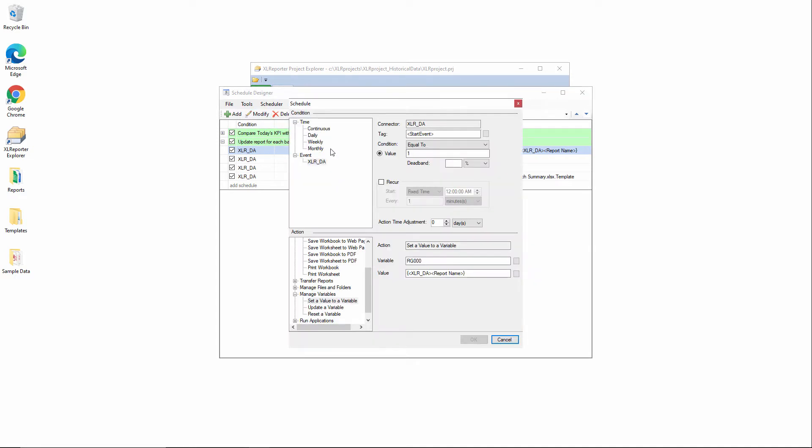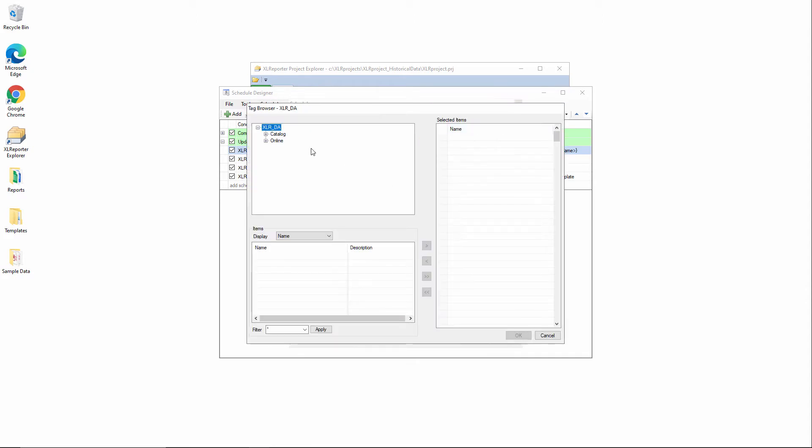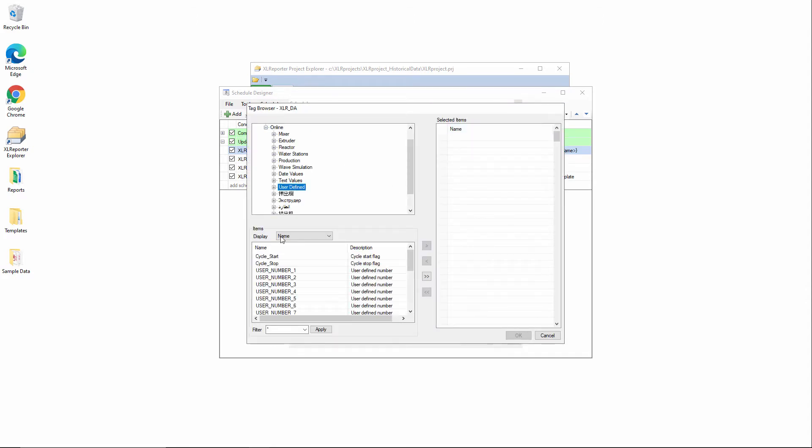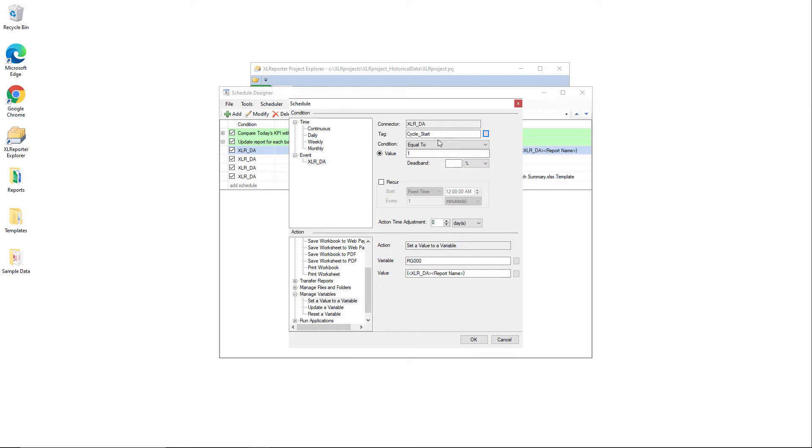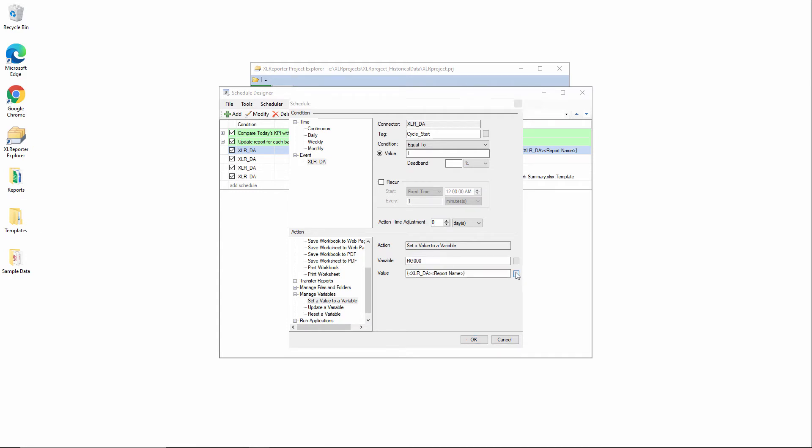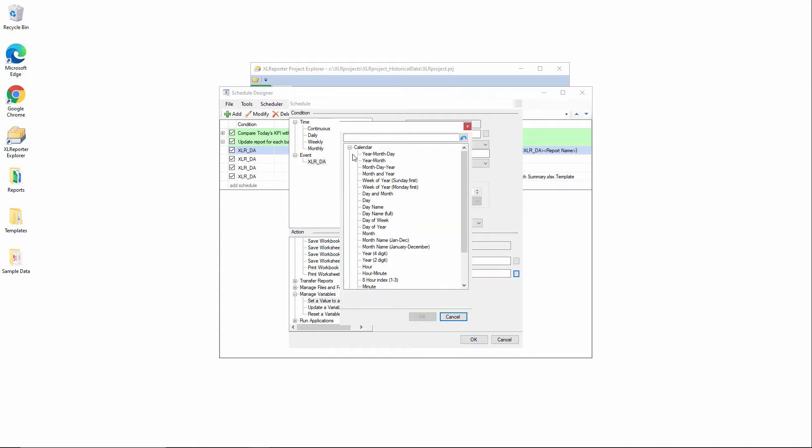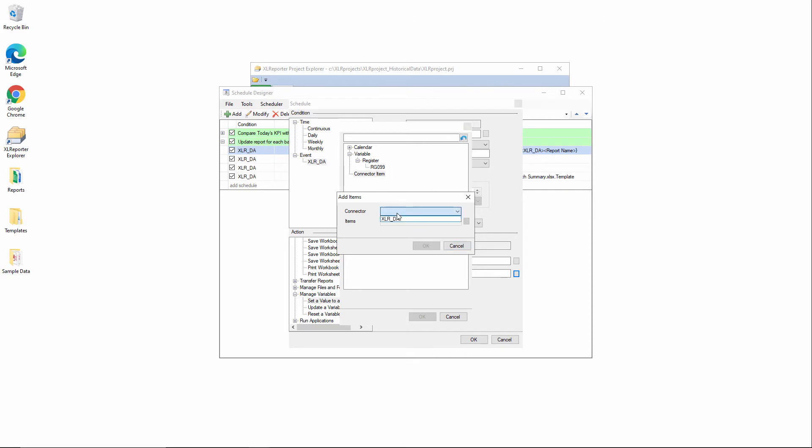I'll select the event condition under my PLC connector with a tag. Let's do, for example, cycle start using the XLRDA simulator here. I'll copy that tag name out because we'll use it for the other three actions. And then we'll assign, when the cycle start transitions to a value of one, we'll assign this XLreporter RG00 variable the value of the cycle ID tag.